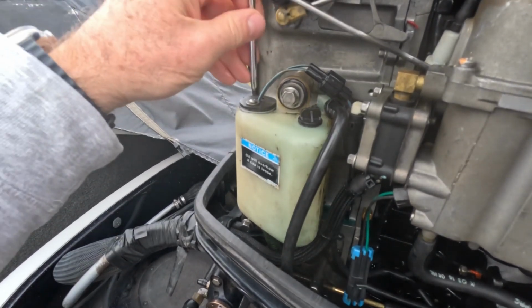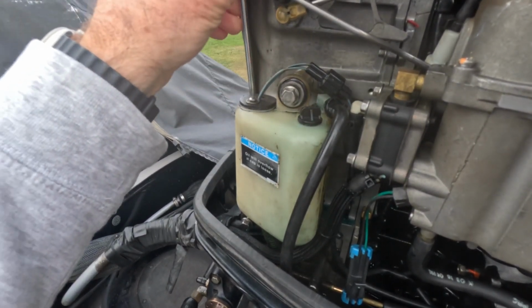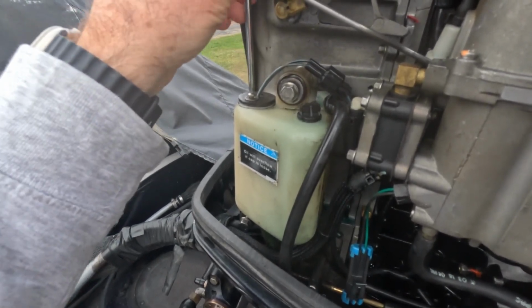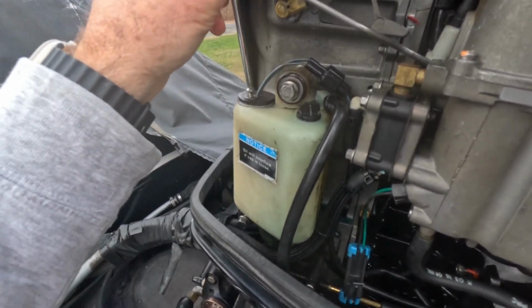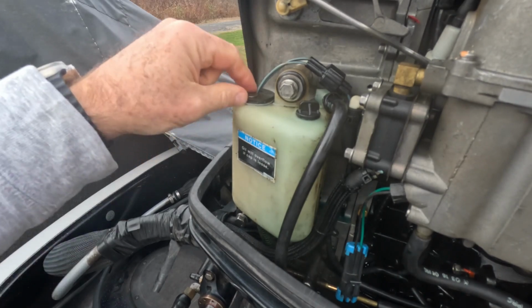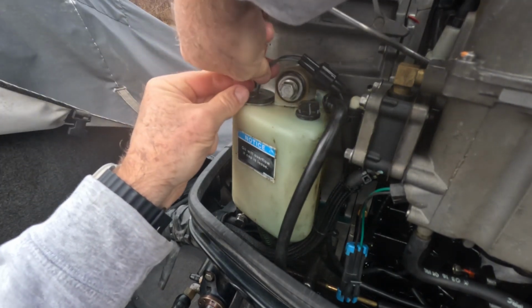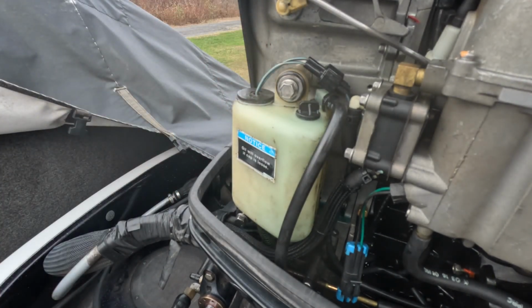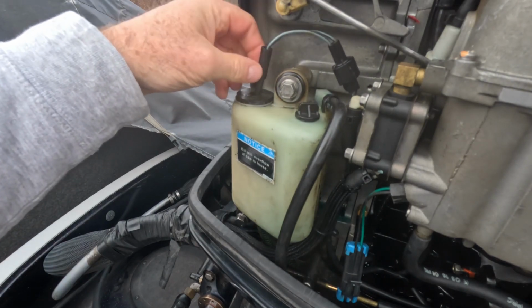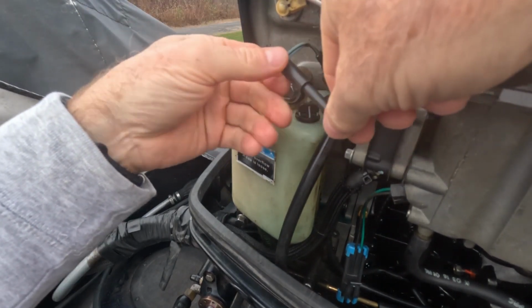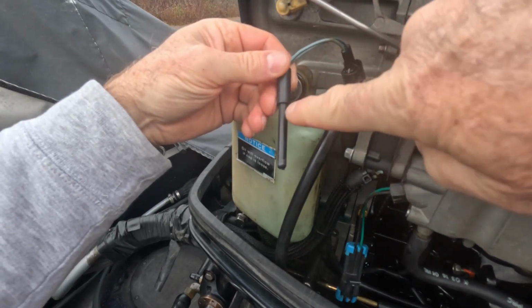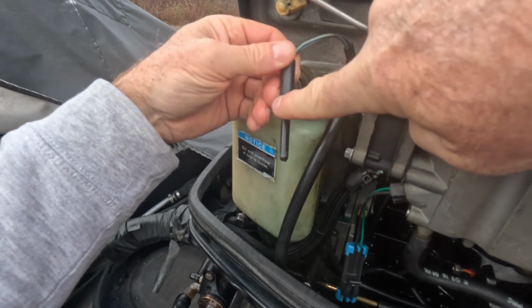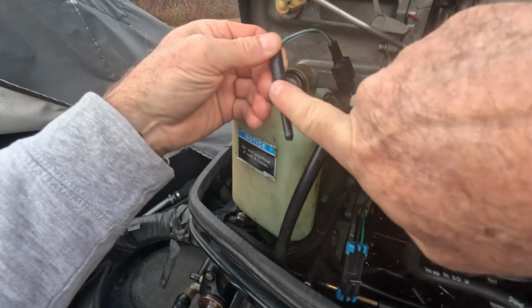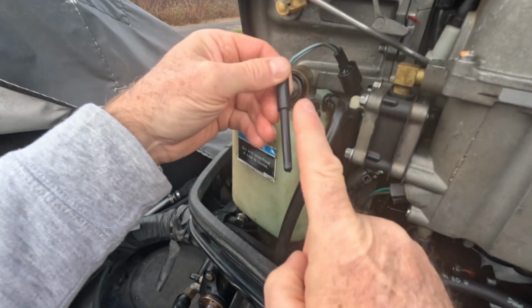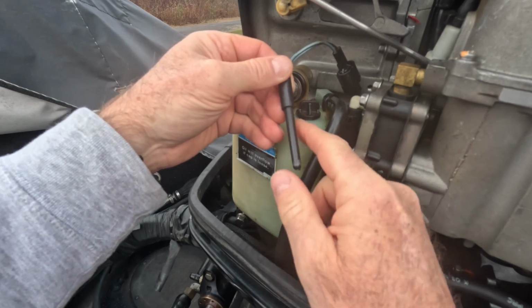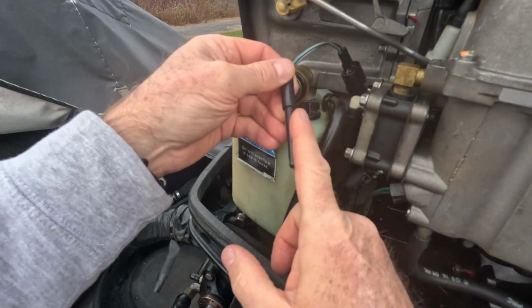So to test that sensor, I want to show you real quick. You just pop this screw off. This screw has a washer, and that washer holds the sensor down so you can't pull it out of there. And the sensor doesn't have any oil on it because it's inside of a housing inside the main tank. But you're going to take a magnet, and you're going to place it under this ridge on this side of the probe. You're going to place a magnet there, and then you're going to want to turn your key on to the on position.